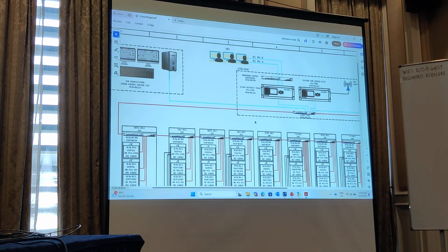So yes, the CID file does connect with the time server, but still Goose doesn't have time quality, so that is the issue now. If you trace it, you can see the time Goose being started or happening, but it's always the time that you're capturing it. Let's say you want to trace back the time, you can't do it. That's what it means by the quality time not being there.